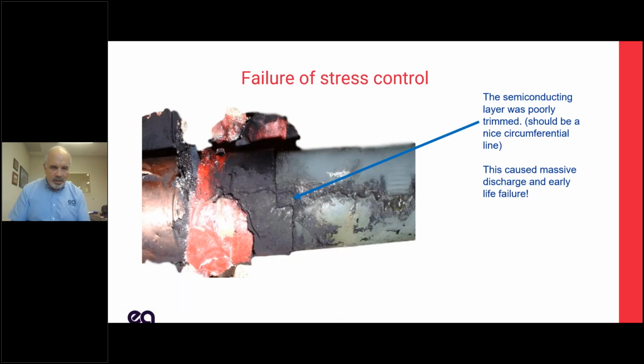So here's an example of something we got in our forensic lab, and this is a cable that was not caught ahead of time. It failed. You can see the XLPE insulation to the right and the semicon layer to the left with a big notch in it. Whoever did this termination was not well trained, or having a bad day, or didn't understand why this was important. You should have had a nice smooth circumferential line of semicon layer. They didn't do that. They ended up with a sharp point, which is going to cause concentration of stress.